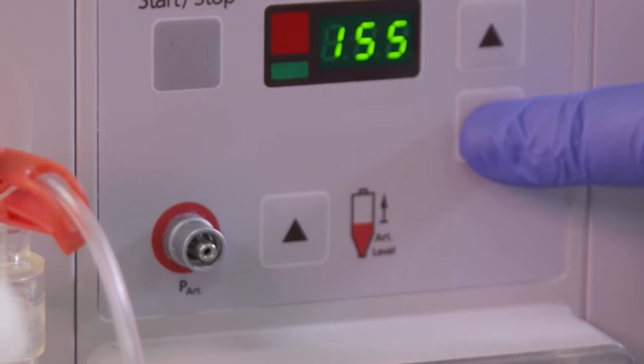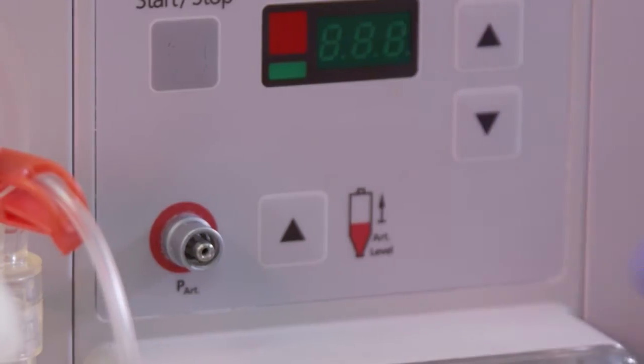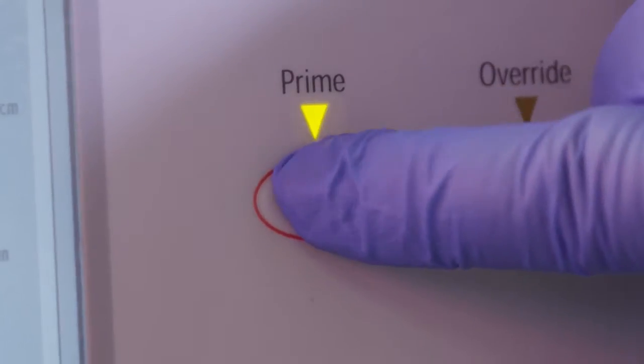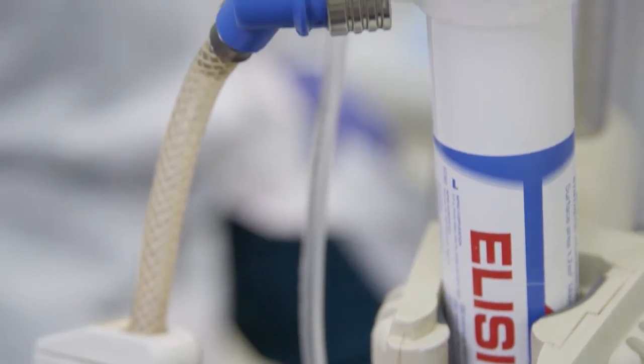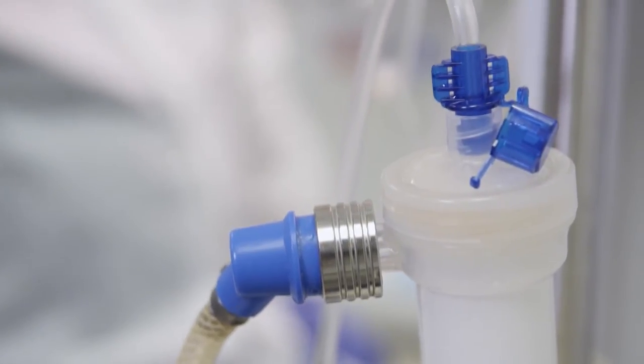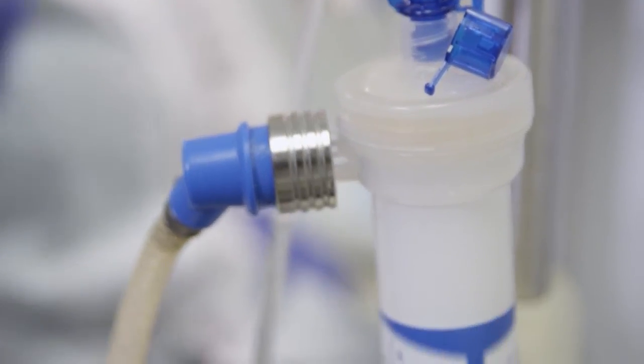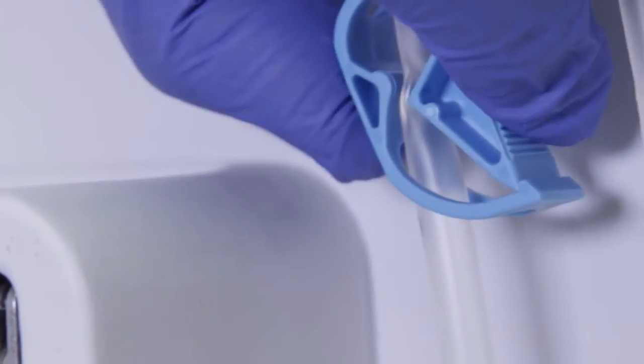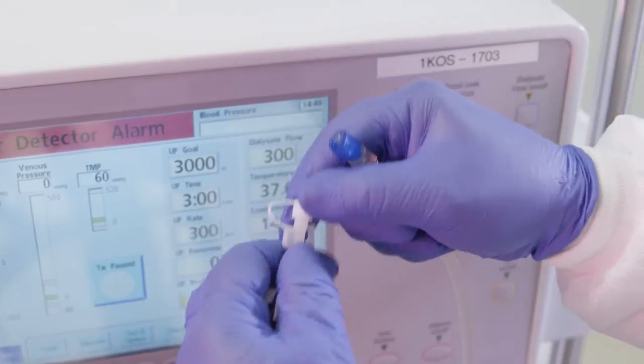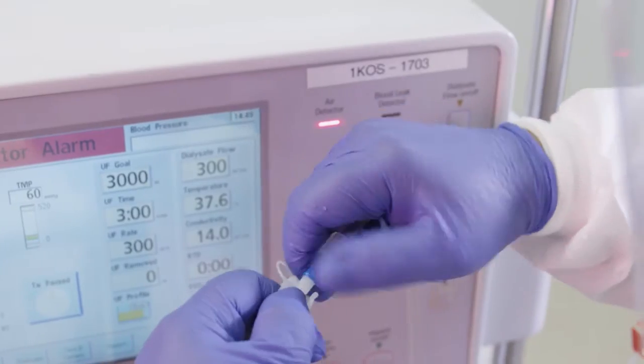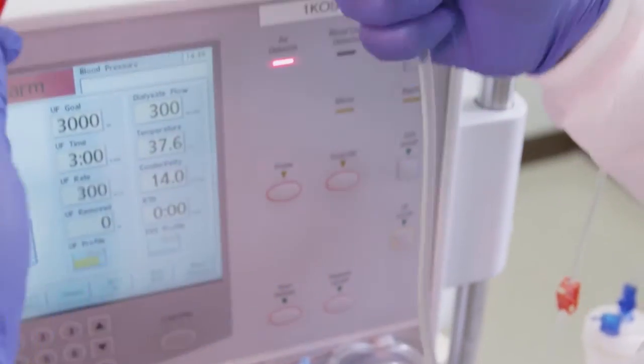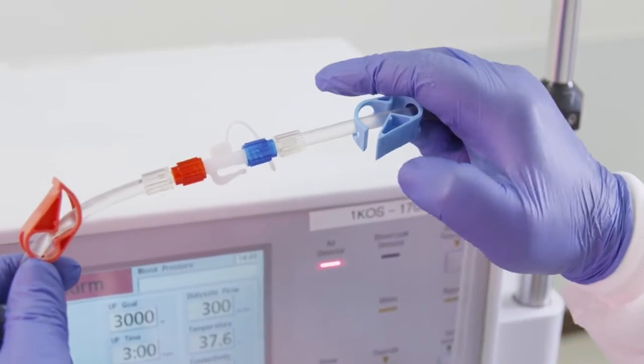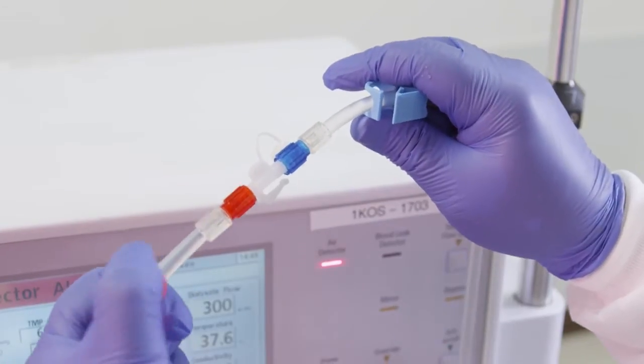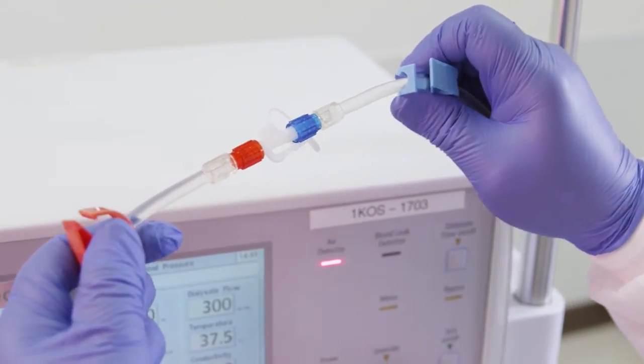Decrease the blood pump speed to 150 milliliters per minute. Press prime and flush the dialyzer and blood lines with at least 300 milliliters of saline until all visible air is removed. Close the large clamp on the patient end of the venous blood line. Connect the arterial and venous lines using the recirculation connector located on the arterial line. Open the large clamps on both lines.